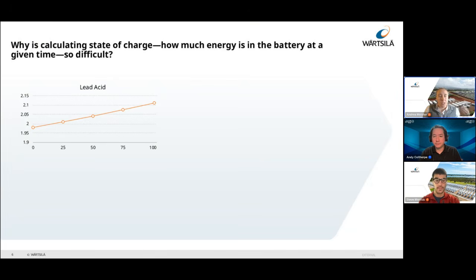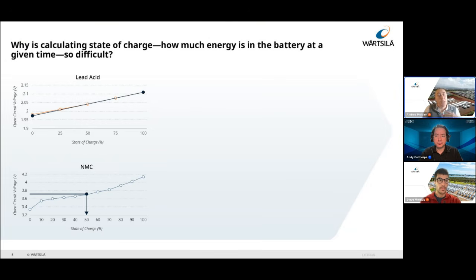So 20, 30 years ago, when lead acid was the dominant chemistry in batteries, it was pretty easy to manage state of charge estimation. Basically, the state of charge versus the measured open circuit voltage is a straight line. You take 2.05 volts per cell, and that's your 50% state of charge. Pretty easy and straightforward. A few years on, when NMC chemistries became more popular, it got a little more challenging because the slope of that line isn't totally linear, but still you can pull off a one-to-one relationship from open circuit voltage to state of charge.